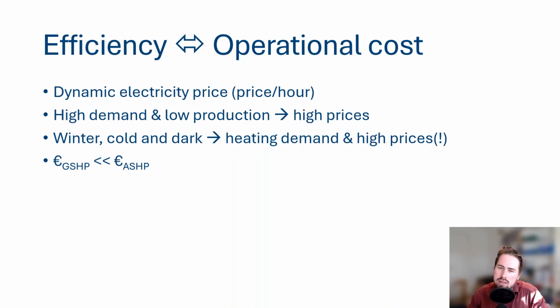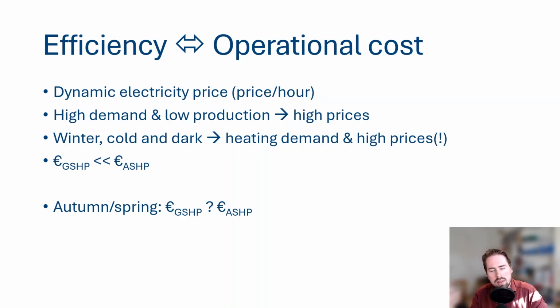It's only in the seasons of autumn and spring that it's not sure which efficiency is better. It really depends on your climate, but when you take this variable electricity price into account, you're almost guaranteed to have a lower operational cost with a ground source heat pump, due to the fact that it's way more efficient at the times that it actually matters.